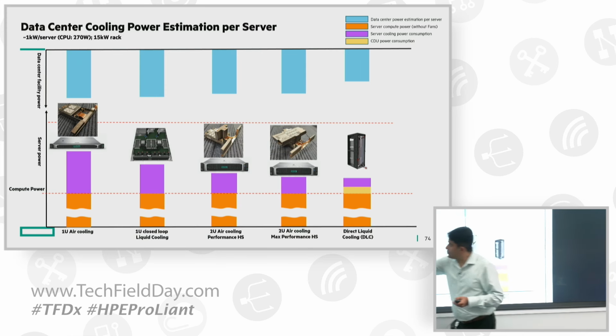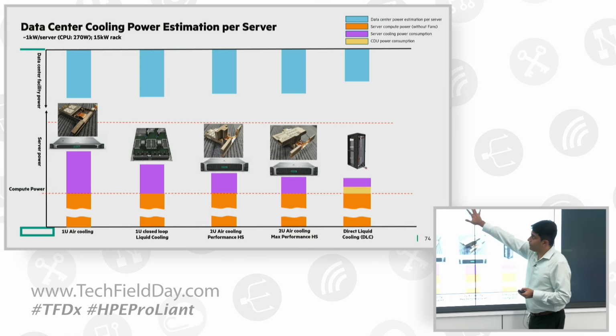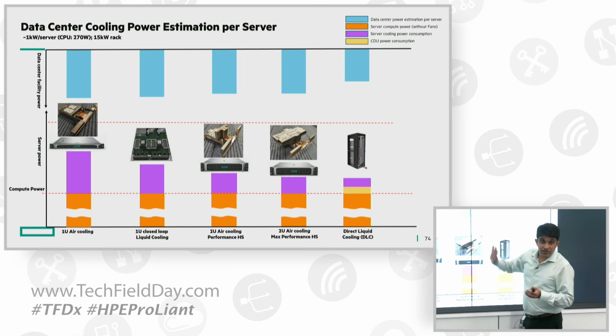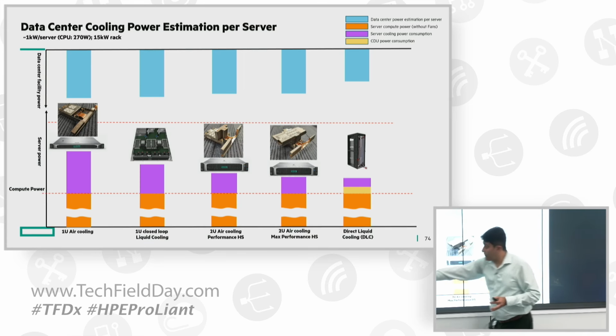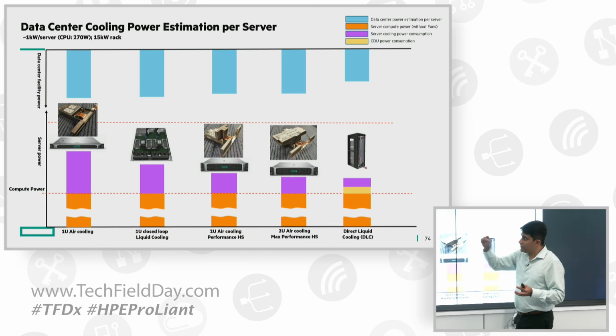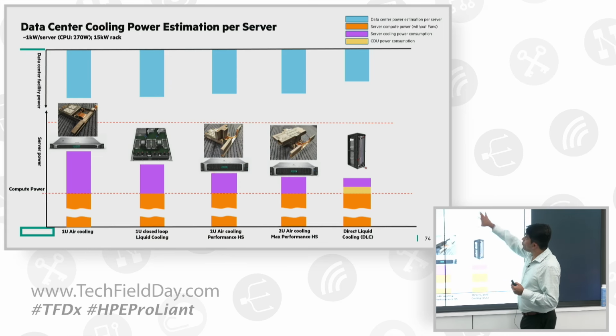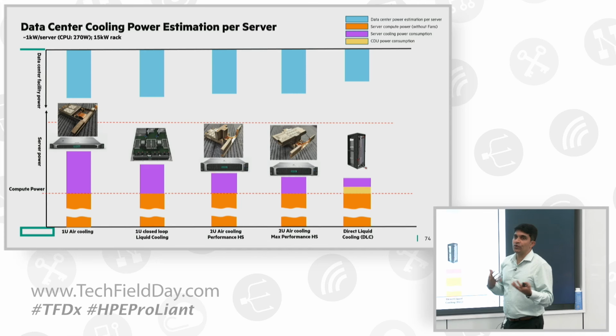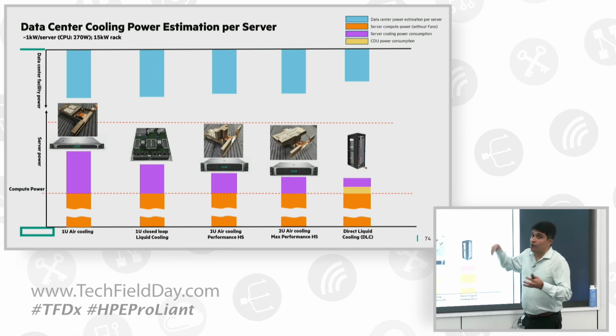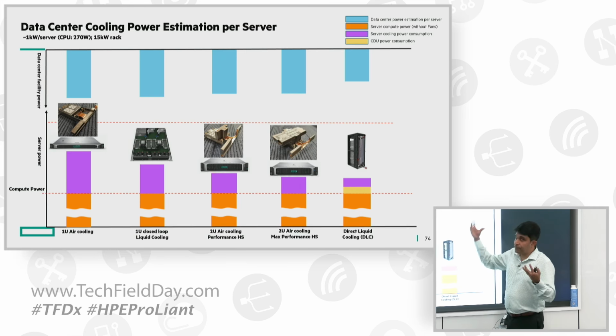If you look at the air cooling, yes, you're saving server or data center power per server, even going from a 1U to a 2U max performance. There's a little server saving, but if you go to DLC, you can tweak your settings, change things that can help save more power. It's not just at a server level, but once you get into DLC, things that need to be considered are your data center efficiency, how you're operating it, and as was mentioned earlier, what is the PUE and where you're operating that.